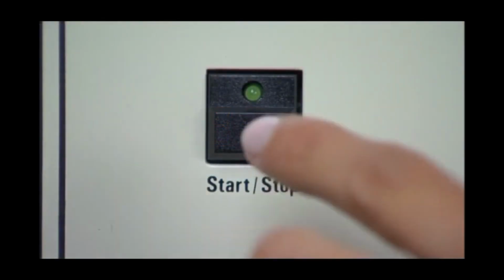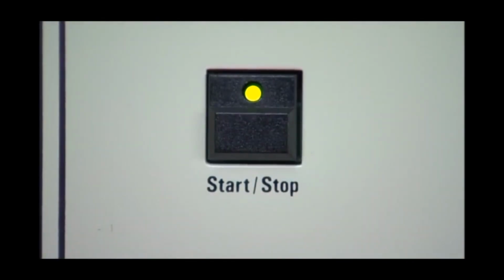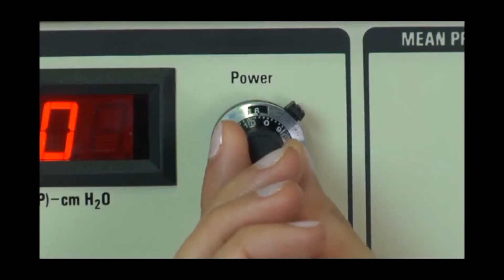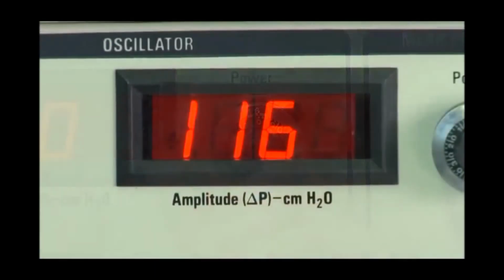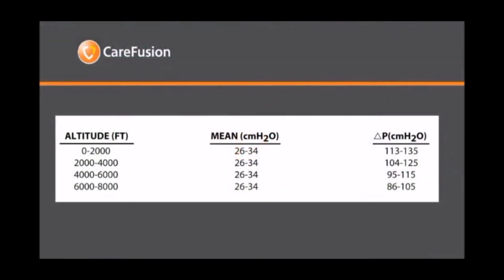Press the Start-Stop button to start the oscillator. Set the power to 6. When a stable amplitude reading is obtained, verify that the amplitude and mean airway pressure readings are within the range specified for your corresponding altitude. Refer to the chart located on the top of the ventilator.